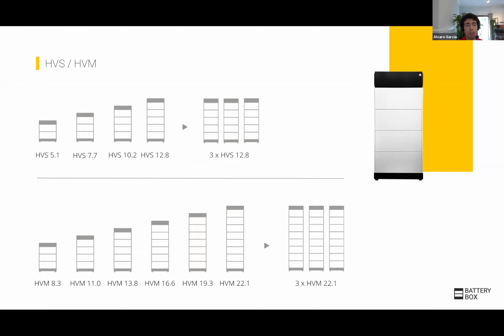In the case of the HVM, each battery module is 51 volts. You start with the smallest system, 150 volts, so three battery modules with 8.3 kilowatt hours, and the largest system with 8 modules in a single tower, that's 22 kilowatt hours. You can have up to 3 of them in parallel, reaching 66 kilowatt hours with a single system, meaning all of this could go with one inverter.